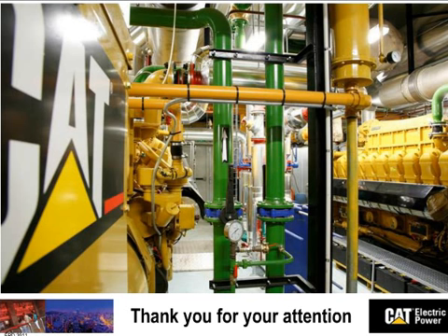Well, these are the 3500A series. We have a 500 kilowatt, 750 kilowatt, 1 megawatt, 1.5 megawatt, and 2 megawatt at high temperature. Depending on the country you operate, you would sometimes be able to run them with a jacket water at 127C. 127C is 260 F. In some other countries, they will limit the temperature to 110 C, which is 230 F.